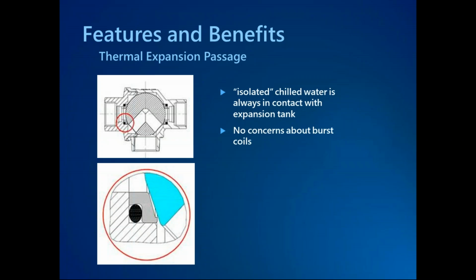So what HCI and some other manufacturers have incorporated is this little safety feature where we just shave off a portion of one of the two ball valves that allow the fluid to always be in contact with the expansion tank in the mechanical room. So any pressure changes due to thermal expansion or contraction are always going to be in contact with the expansion tank in the mechanical room.